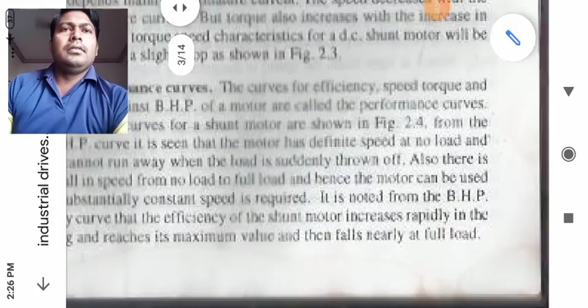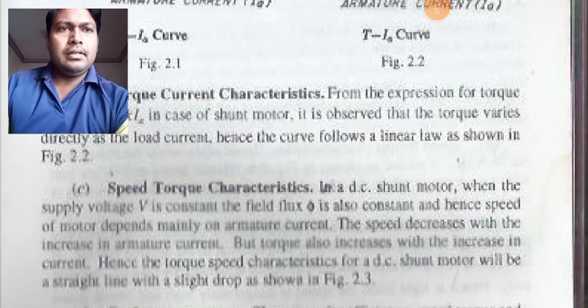Speed torque characteristics. In a DC shunt motor, when the supply voltage V is constant, the field flux phi is also constant, and hence the speed of the motor depends upon the armature current. The speed decreases with the increase in the armature current, but the torque increases with the increase in current. Hence the torque speed characteristic for a DC shunt motor will be a straight line with a slight droop, as in the figure which I have shown you now.